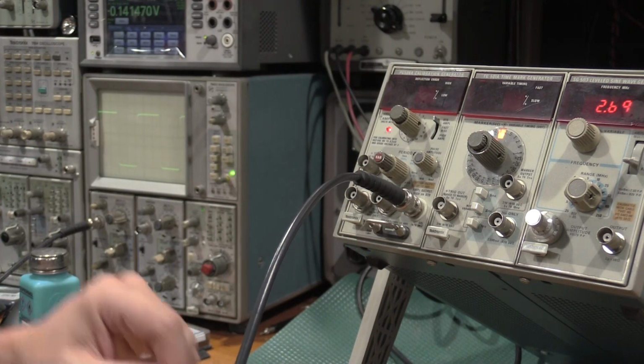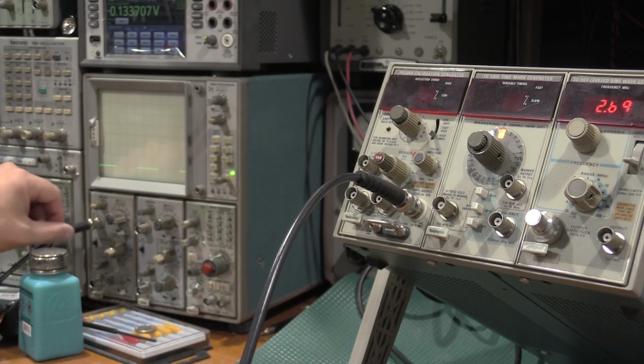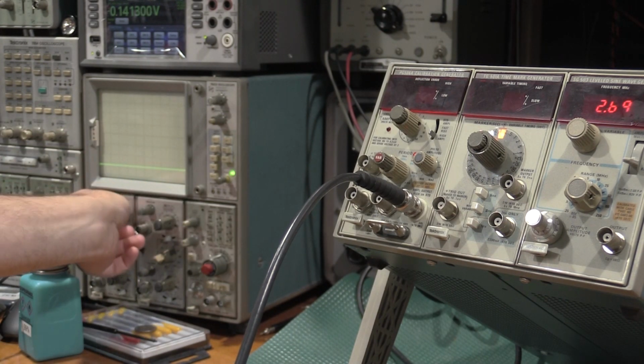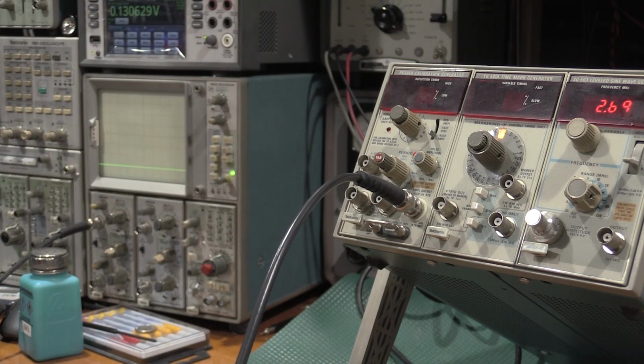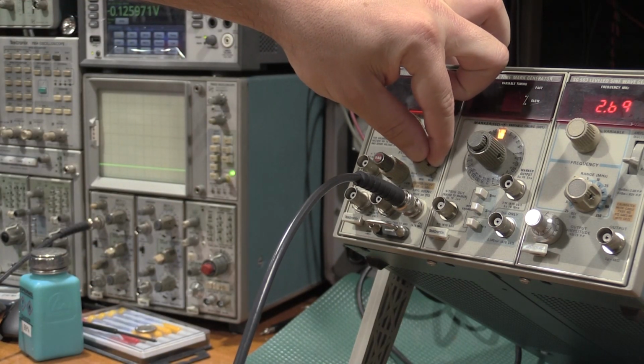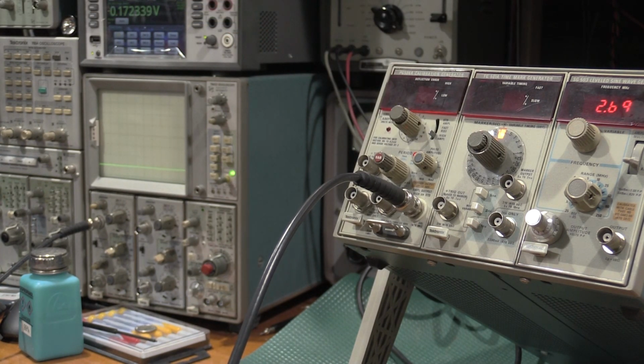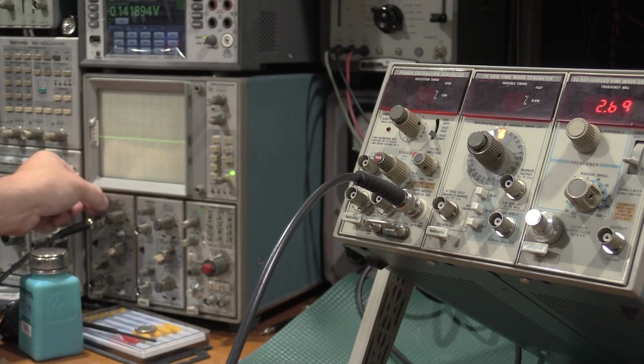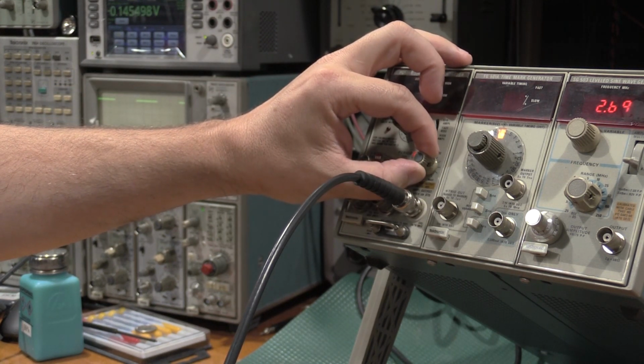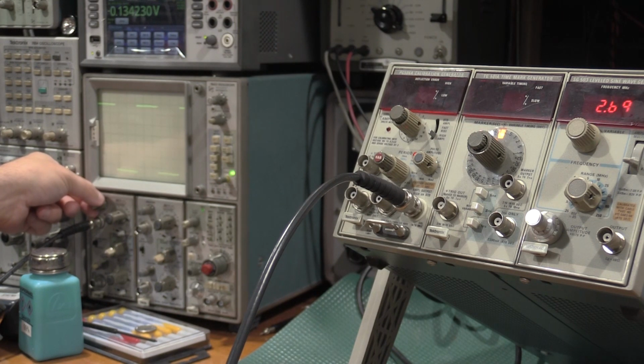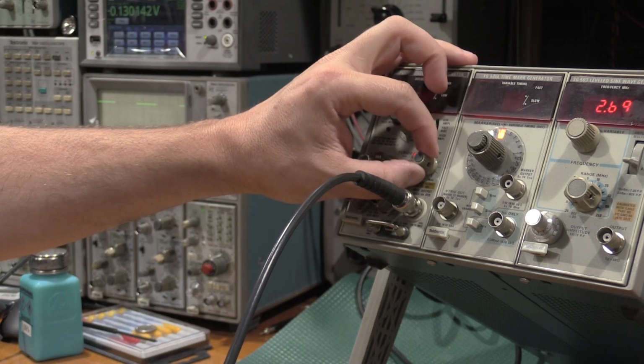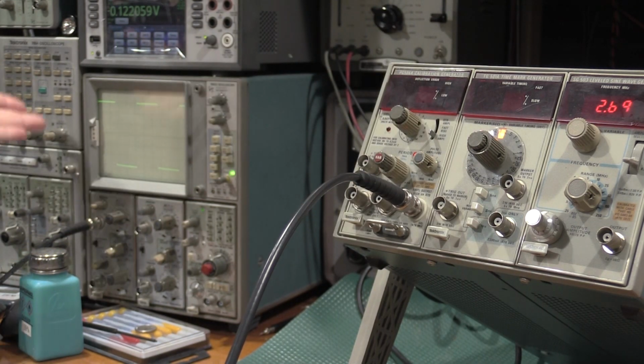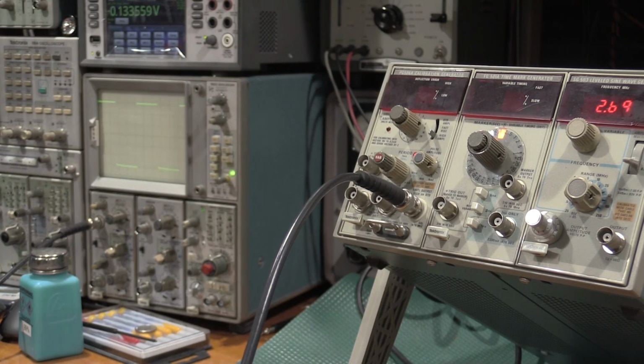Let's check our high amplitude now. Kick down here. We'll go to 5 volts a division. We'll dial up the amplitude so you guys can see it. Yep, that's going to be a problem. Here we go. Got some capacitive coupling. I got to rock the switch back and forth on the scope. The contacts are a little dirty on that one. But our high amplitude, and it actually looks better too. It was falling off a little bit, so that looks a lot healthier.